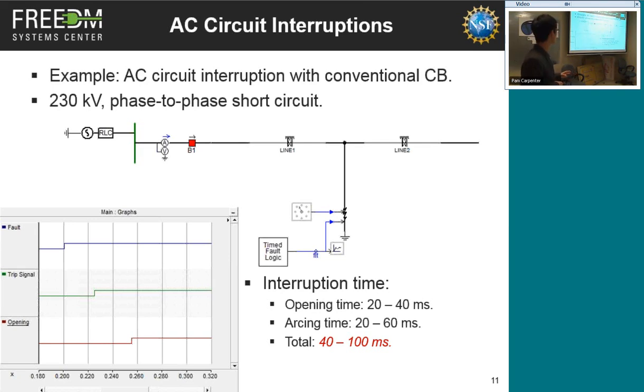I did a simulation. We have a transmission line here, and we assume a fault happens here. This B1 is a circuit breaker. What happens if there's a fault? This is a three-phase system, and we have assumed a phase-to-phase fault here. Looking at the sequence: at this moment the fault happens, at this moment the relay detects the fault and sends out a trip signal, and at this moment the contact of the circuit breaker actually opens. So there have been a few delays here, and these should all be counted into the total time to interrupt a fault.